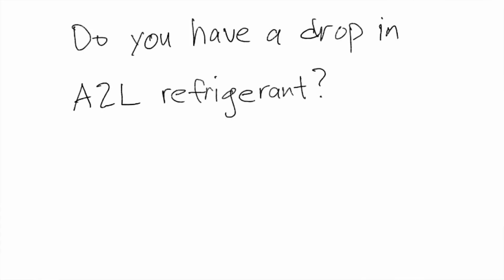Another question that I got during the presentation was, do you have a drop-in A2L refrigerant? The short answer is no. I represent Toshiba Carrier and Carrier here in Southern California. We don't have one, but we are working towards a refrigerant change come 2025, 2026, I believe. And the refrigerant that we're probably going to go towards is R454B. I know R32 is the refrigerant of choice for some of the other markets in the world, but here in North America, it looks like we're going to be moving towards R454B. So right now, we don't have a drop-in refrigerant. We're going to use R410A from now until we're required to make that change.